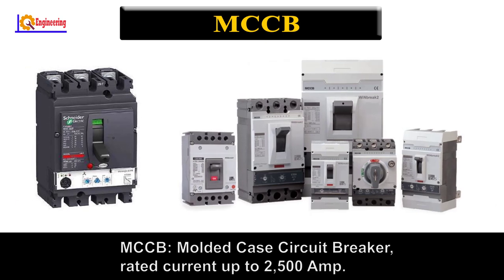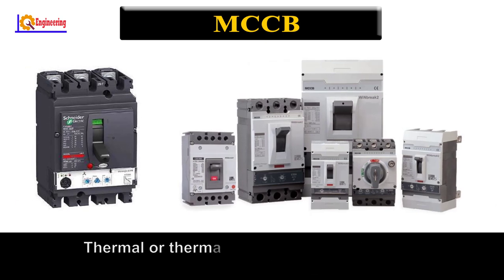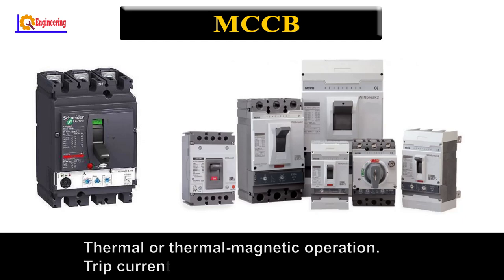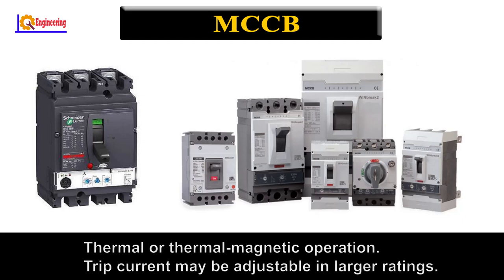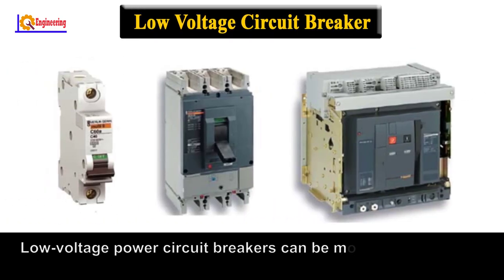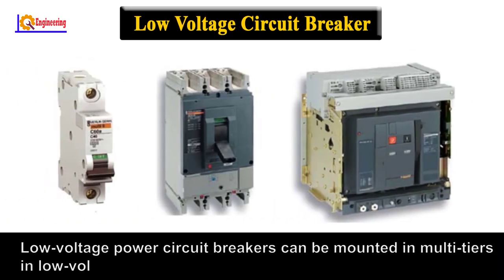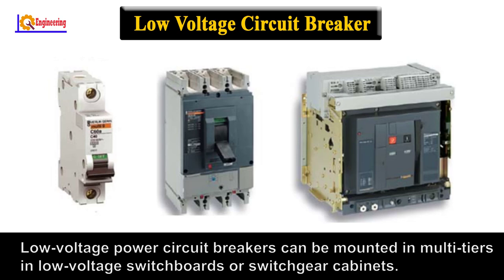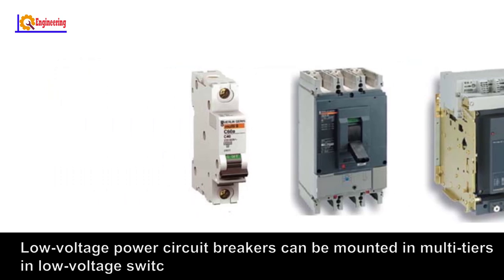MCCB — Molded Case Circuit Breaker: rated current up to 2500A, thermal or thermal-magnetic operation, trip current may be adjustable in larger ratings. Low voltage power circuit breakers can be mounted in multi-tier low-voltage switchboards or switchgear cabinets.